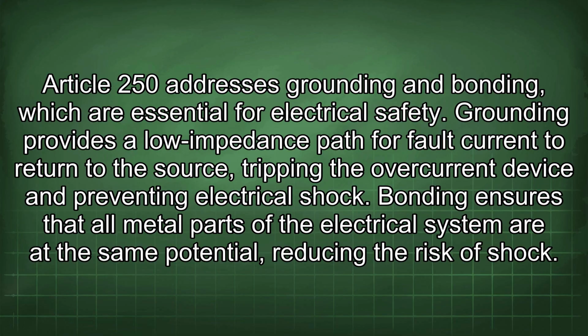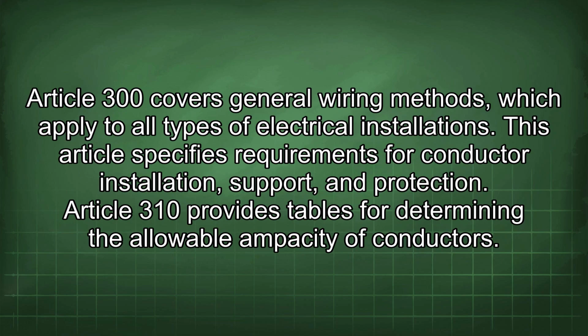Article 250 addresses grounding and bonding, which are essential for electrical safety. Grounding provides a low impedance path for fault current to return to the source, tripping the overcurrent device and preventing electrical shock. Bonding ensures that all metal parts of the electrical system are at the same potential, reducing the risk of shock. Article 300 covers general wiring methods, which apply to all types of electrical installations. This article specifies requirements for conductor installation, support, and protection.